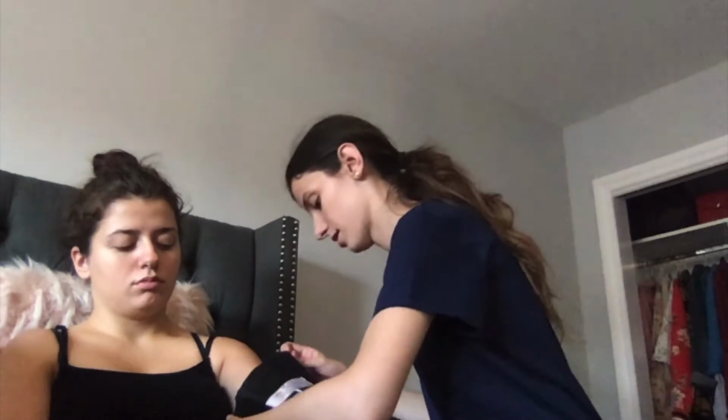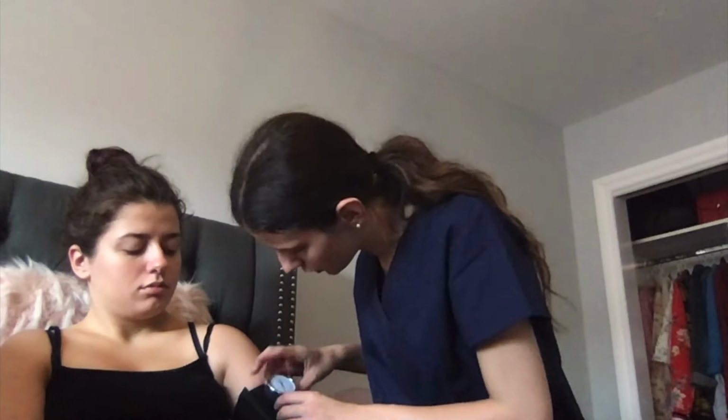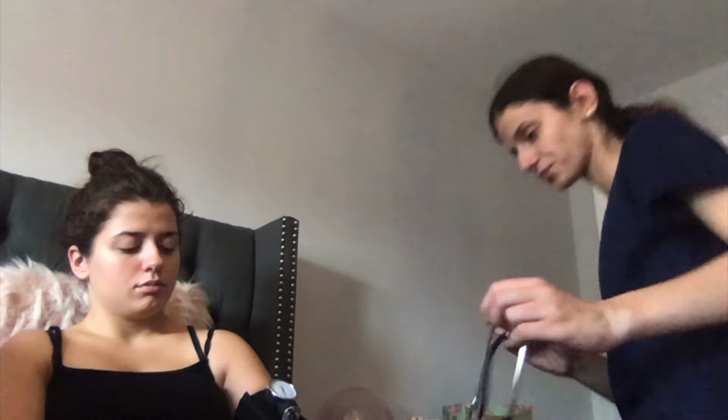the arm. Also tighten it so that it's appropriate for the patient. It shouldn't be too tight and shouldn't be too loose. The gauge over here has to be recalibrated a minimum of once a year, so that it points to 0. And you can place that up here while you measure. The bulb should be tightened to the fullest before pumping.